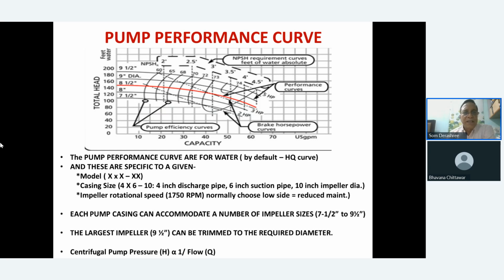And you will see as the flow increases, the head goes down. So head is actually inversely related to flow. This is a very typical characteristic of centrifugal pumps, which make up 80% to 90% of the population in any industry. That's why we are talking mainly about centrifugal pumps.